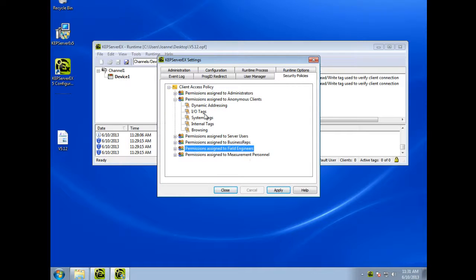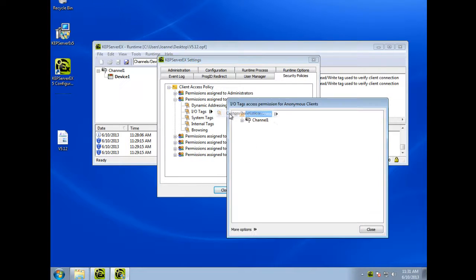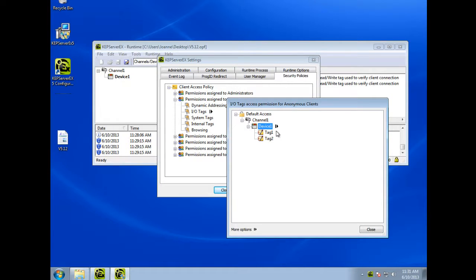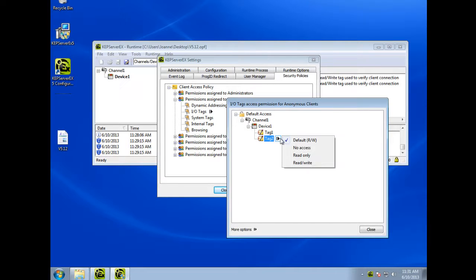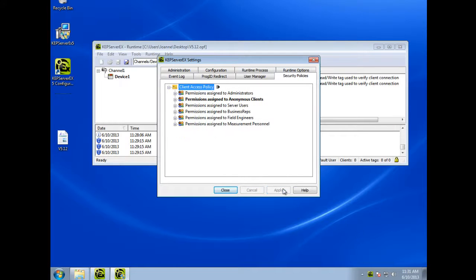It allows server administrators to configure role-based security rules that define read, write, and browse access permissions of server items down to the tag level. For example, tag 2 in channel 1 device 1 can be set to no access for anonymous OPC DA clients.